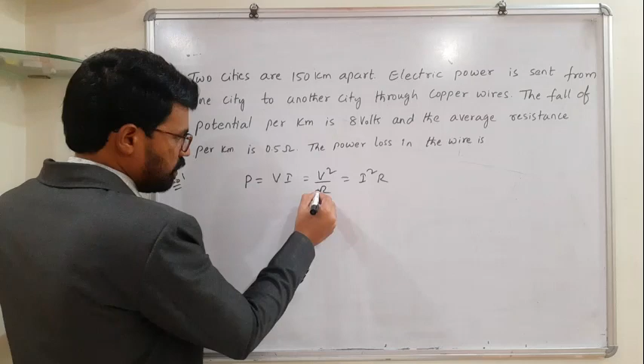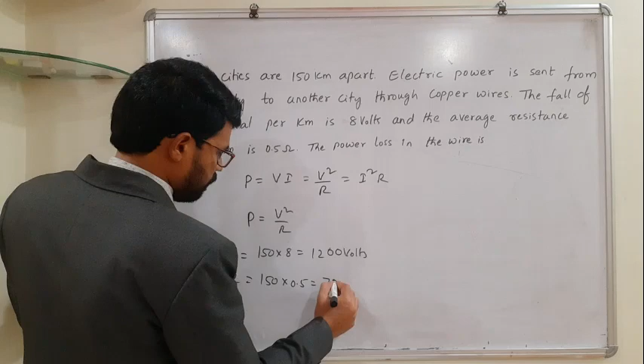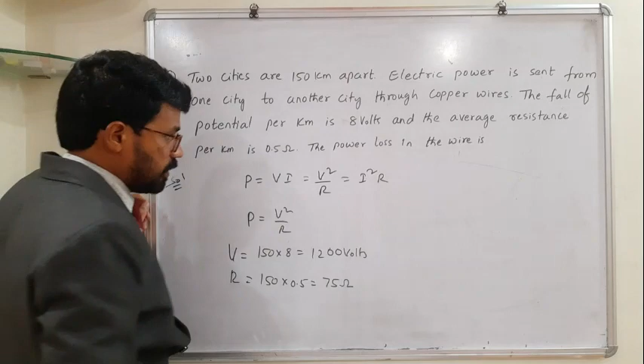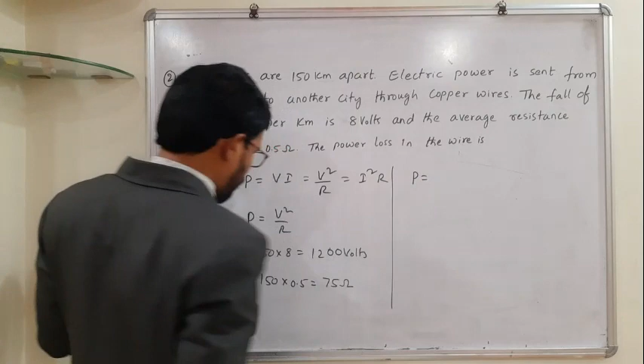1200 volts. What about resistance? Per kilometer it is 0.5. So how many kilometers of wire? 150. So 150 into 0.5. So what you will have? 75 ohms. So this is the total resistance offered by the copper wire. So let us substitute these two values in this equation and find out what the power loss is. Power loss P is equal to V square, 1200 square, or you can write like this, 12 square into 10 power 4 divided by 75.